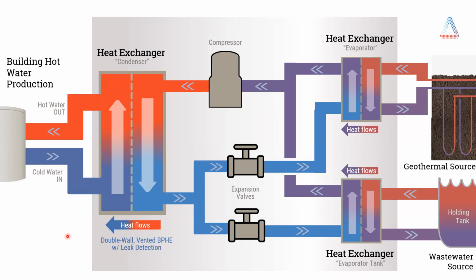So everyone's familiar with the overall use of a heat pump and a compressor system: drawing energy from a source, putting it into the refrigerant, using the compressor to boost the temperature and the pressure within the refrigerant, and sending that energy into a condenser, outputting hot water, which would be used for many uses within the building. In this type of heat pump, it can actually be a dual refrigerant circuit, utilizing two evaporators. The first, which is paired with our wastewater source, takes energy from wastewater and absorbs that energy across the wall of the evaporator into the refrigerant circuit to be used for that hot water output purpose.